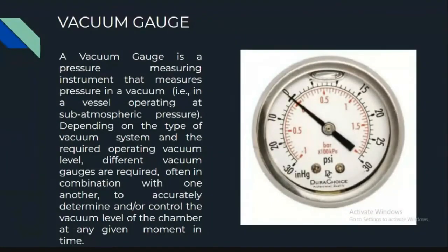Good afternoon, sir. A vacuum gauge is a pressure measuring instrument that measures pressure in a vacuum, that is, vessels operating at subatmospheric pressure. Depending on the type of vacuum system and the required operating vacuum level, different vacuum gauges are often required in combination with one another to accurately determine and control the vacuum level of the chamber at any given moment.